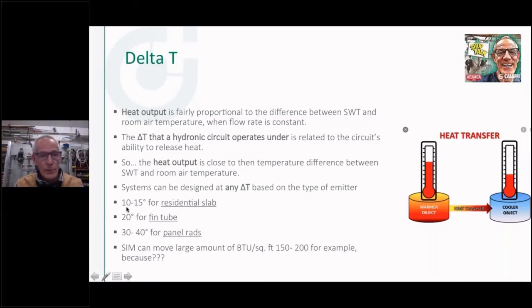Again, you could jump around anywhere within this range. For a radiant slab, we try to keep that delta T fairly tight, so there's a consistent temperature across the floor. If we walk from one end of the zone to the other end of the loop, it feels about the same temperature. So we usually want to keep a 10 to 15 degree delta T. That doesn't mean it won't go lower or wider than that. Fin tube, 20 seems to be the number there. We can keep it at that. It could be 25, it could be 15. Panel radiators, we can go a little bit wider. A 30 to 40 degree delta T is a fairly common design for a panel radiator because we've got a lot of surface area to work with there.